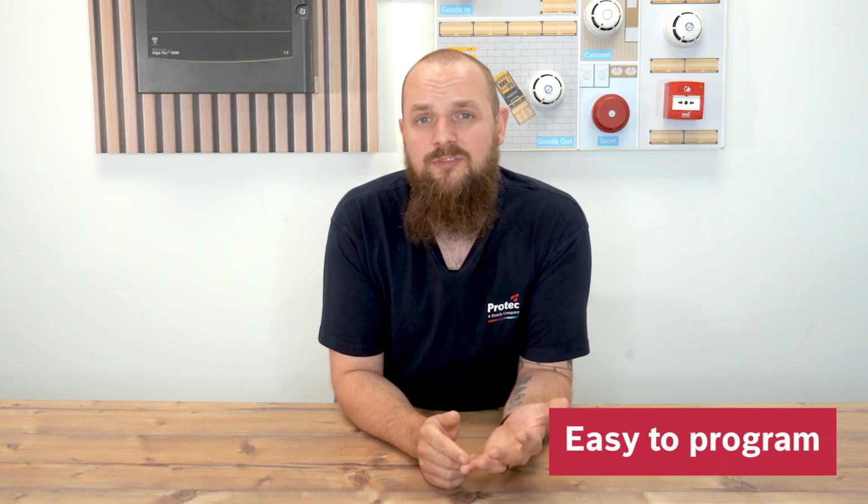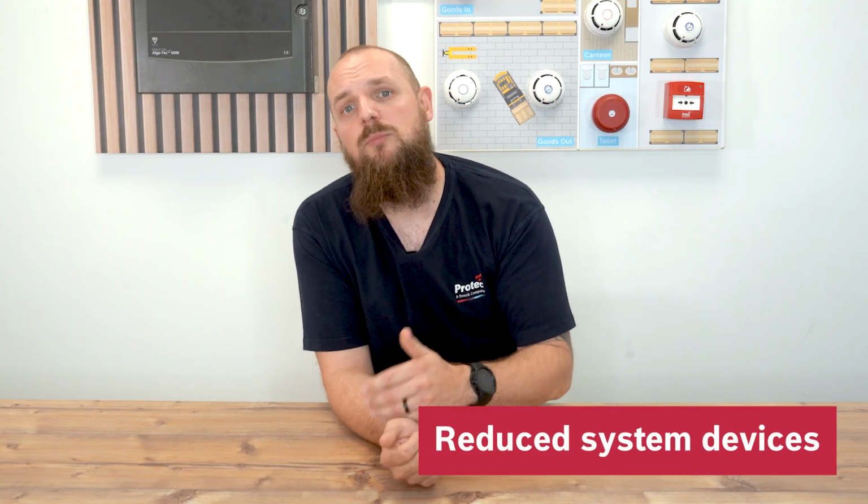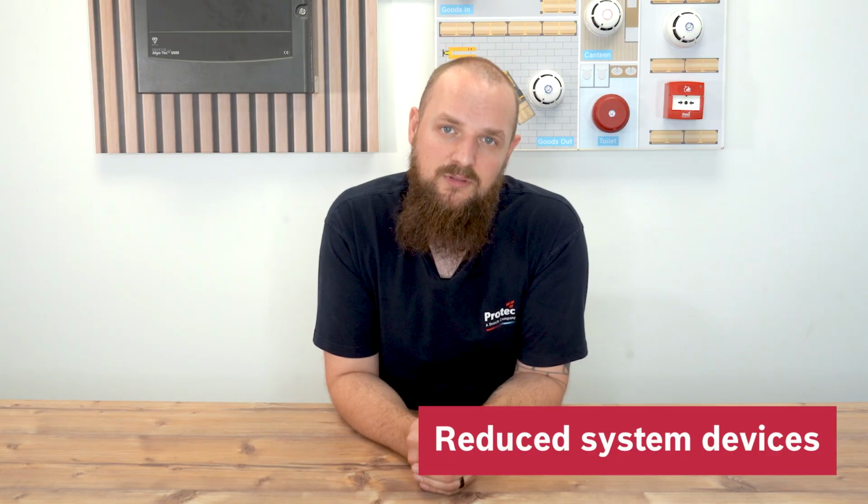Okay, let's wrap up this video with a few key takeaways on the new LP4IO unit. So we've got 4 inputs and 4 outputs, which are fully configurable using the dip switches on the front of the unit. They're also very easy to program using the barcode fast addressing system and the PC application for the 6500 software. We can use both the matrix and Boolean logic to program these devices. These can replace up to 8 standalone devices out in the field, meaning we have less addresses to contend with and less current draw on any single loop as well.